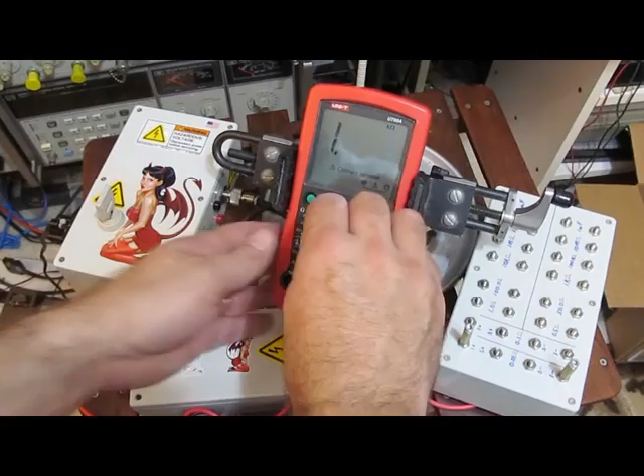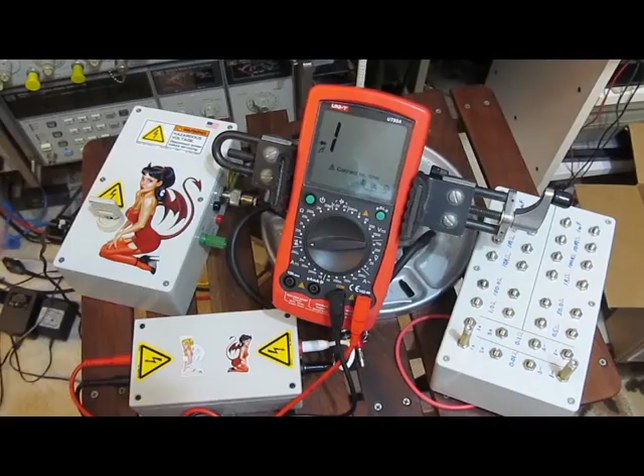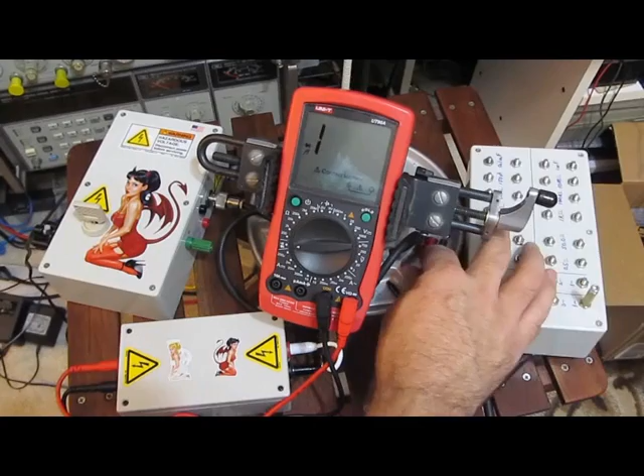So let's go ahead, we'll put her in diode mode. You can see the meter doesn't even flinch. We could have the probes connected to any of these inputs now. As long as we've got this attenuator in line, that should protect this meter with no problems at all. It's actually designed for upwards of 12 to 14,000 volts. The probe leads here would definitely fail long before this box does. You can see it in ohms mode.